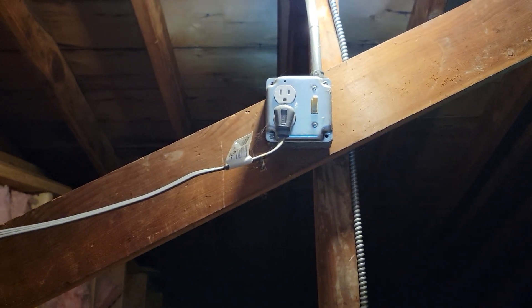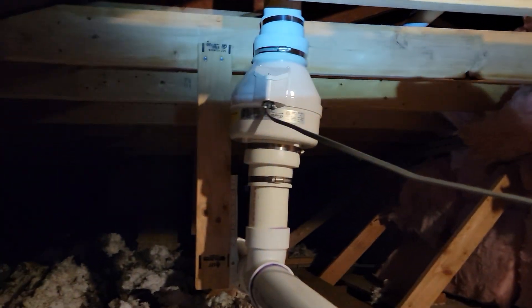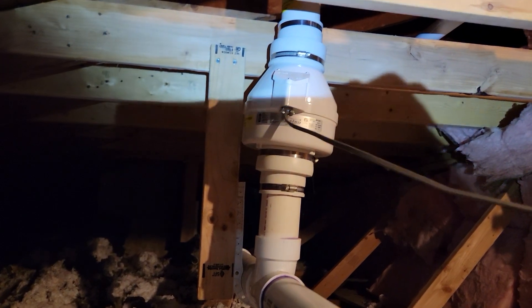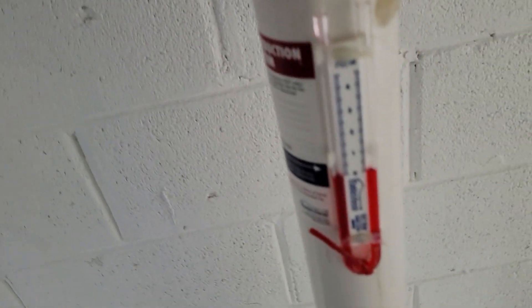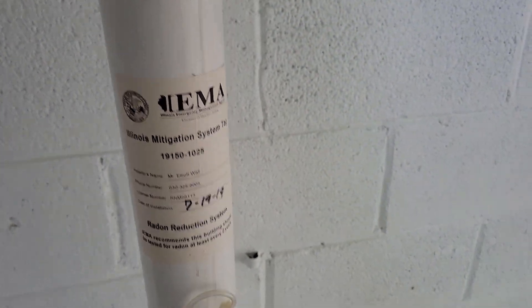I'm in an attic today. You can see we got an electrical cord here, and this cord goes to a radon reduction system — that's like an exhaust fan. The home has radon, but the problem is the pump isn't going. When I come down to look for the manometer, you can see the liquid level is off, so that radon system needs to be checked.